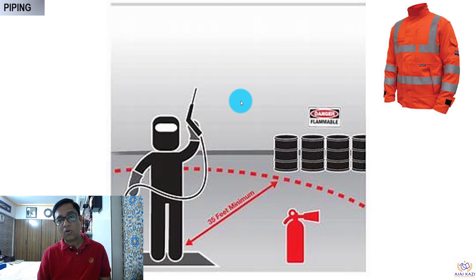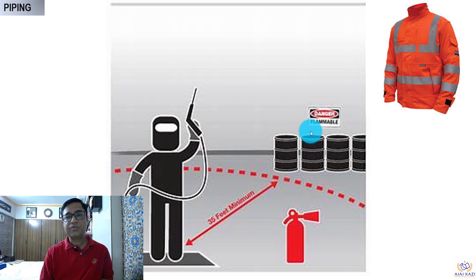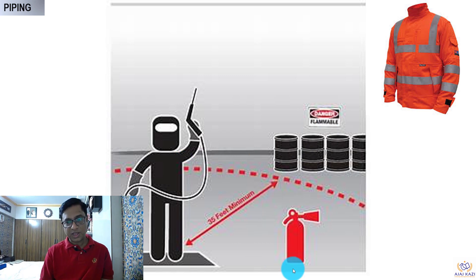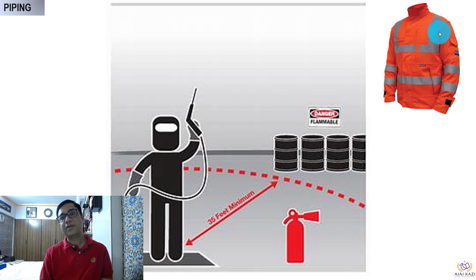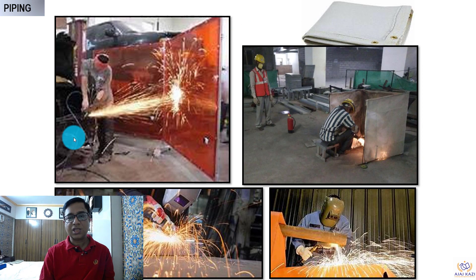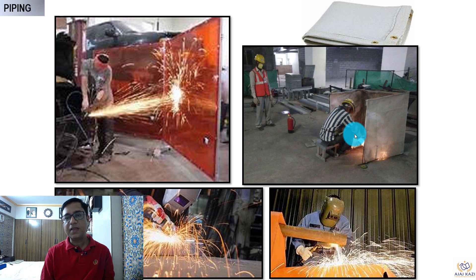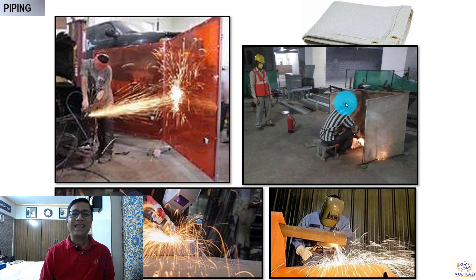Whenever we do hot work, please ensure we are away from combustible material. Per standard, 35 feet is the minimum distance required between combustible material and where hot work is performed. There must be a fire extinguisher present, and it is recommended that people doing hot work are provided with a fire blanket jacket to protect against heat exposure. The work is covered by fire blankets so sparks do not escape; if anything goes wrong, the fire extinguisher and fire watcher take care of it.